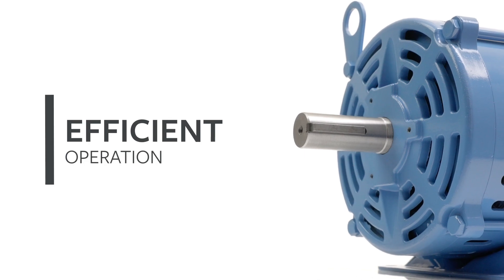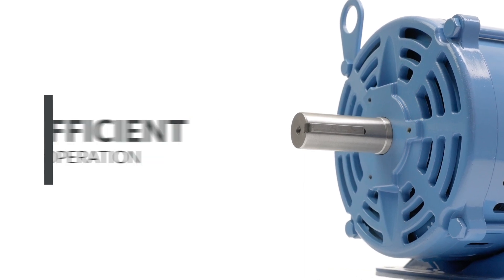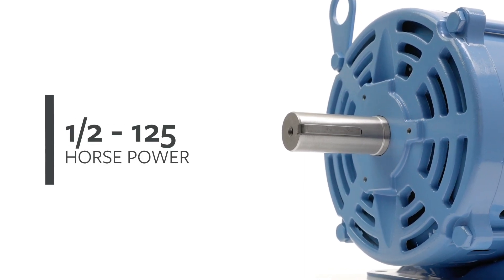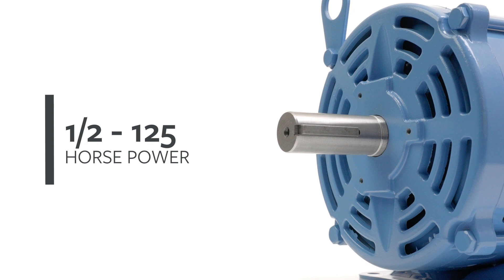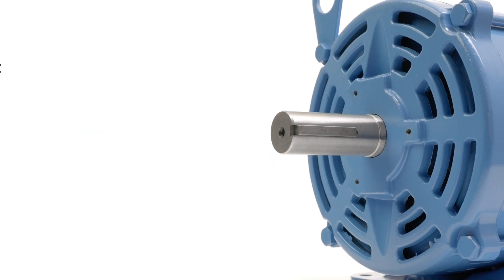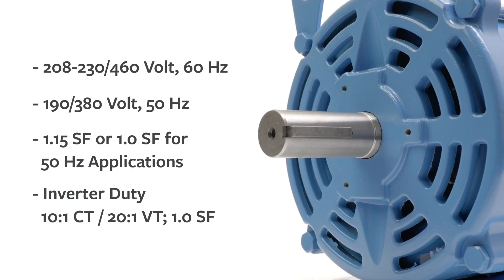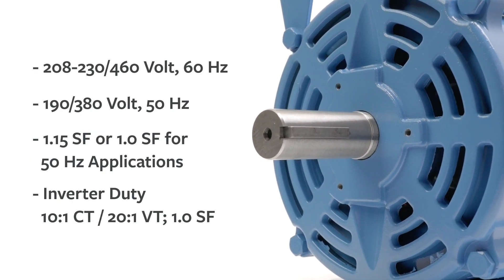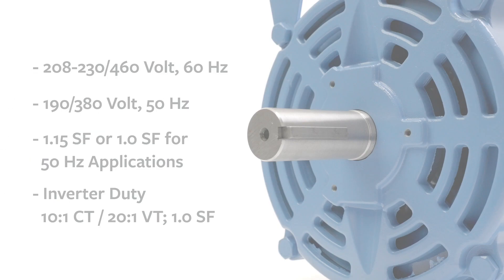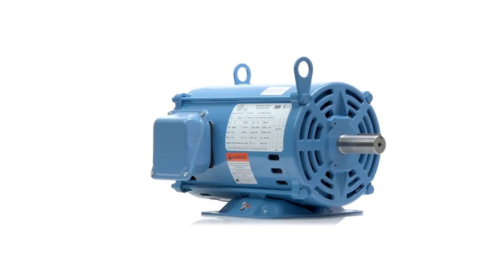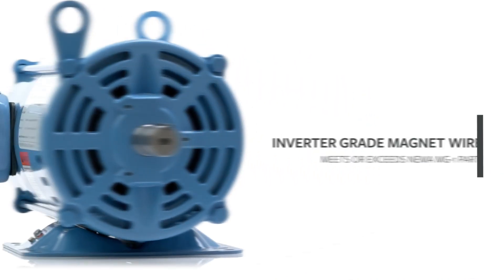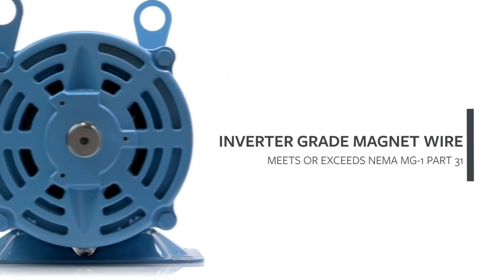Each motor operates at premium efficiency specifications. They are available from 1/2 to 125 horsepower, 50 or 60 hertz configurations, meet NEMA specifications, and provide inverter duty and service factors suitable for ODP motor applications.